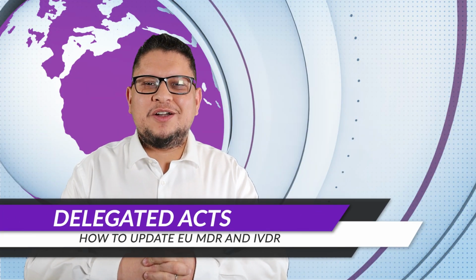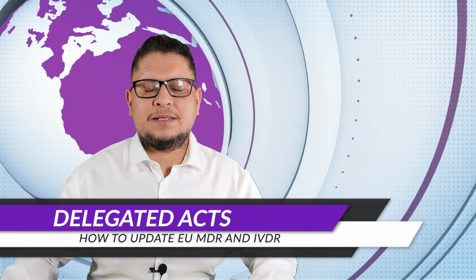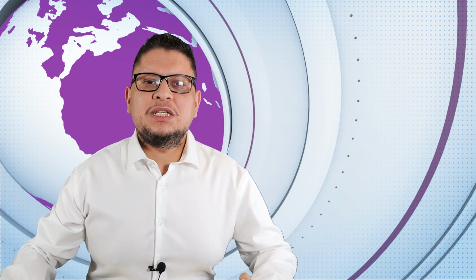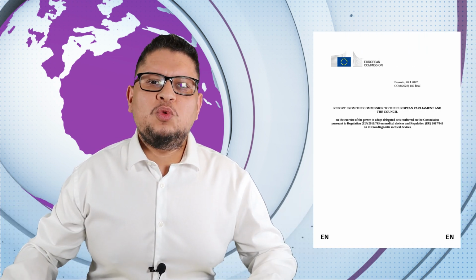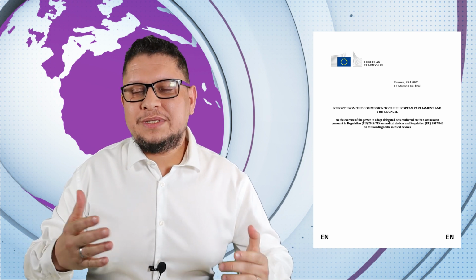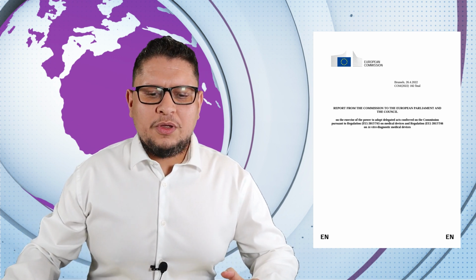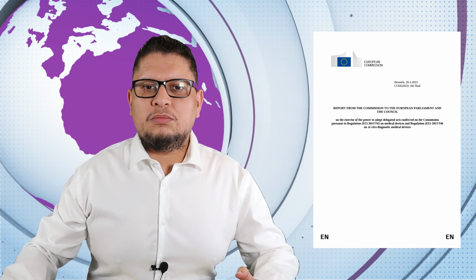Okay, the EU Commission is also providing some information related to the delegated act. So delegated acts are mainly acts that will be issued by the EU Commission to update the EU MDR or IVDR. So how this is working, what are exactly the scopes? In this document, it's mentioned that the delegated acts will be done, for example, to update the Annex 16 list. The Annex 16 covers the products that have no medical purpose, and a delegated act can be issued to update this list. Now we actually have 6 categories inside. Maybe there will be a 7th category, or maybe there will be some clarification on the categories that are already available. So this can be done through a delegated act.